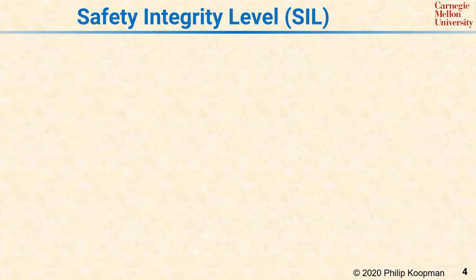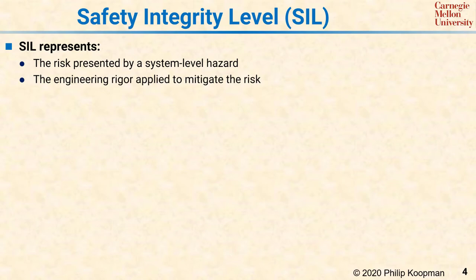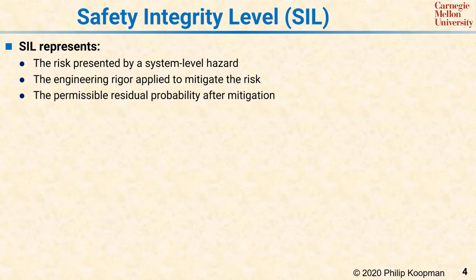The general strategy for building critical systems is to first define a safety integrity level, or SIL, that is required, and then use that SIL to guide the system design process. In practice, a SIL represents three related things: first, the risk presented by a system level hazard, with a high SIL being considered extremely hazardous and a low SIL considered minimally hazardous; second, the amount of engineering rigor and system cost applied to mitigate that risk; and third, an acceptable target for the residual probability of system failure after mitigation has been completed.